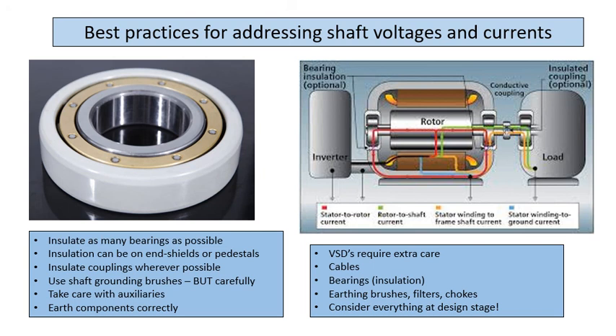Okay, best practices. This is what I came up with. Insulate as many bearings as possible. Your insulation can be on your end shields or pedestals. Insulate couplings wherever possible. I understand that's quite expensive. Use shaft grounding brushes, but carefully. In other words, don't just use them all over the place. Put them in the right place and keep them to a minimum. Take care with auxiliaries and then earth components correctly. VSDs require extra care: cables, bearings, insulation, earthing brushes, filters, chokes, and then, very important, consider everything at the design stage. Don't try and resolve it after the fact when you've got problems on site.